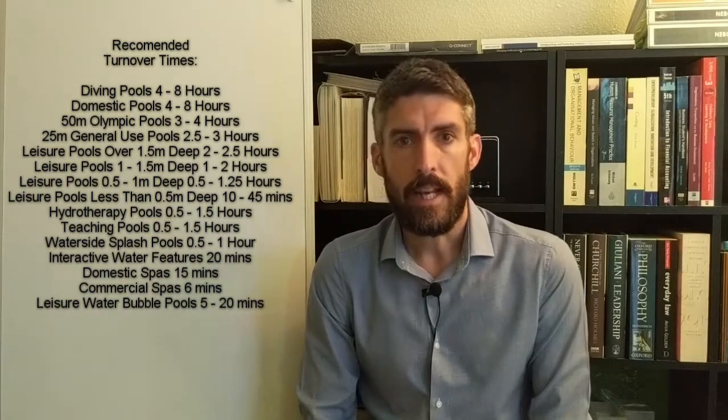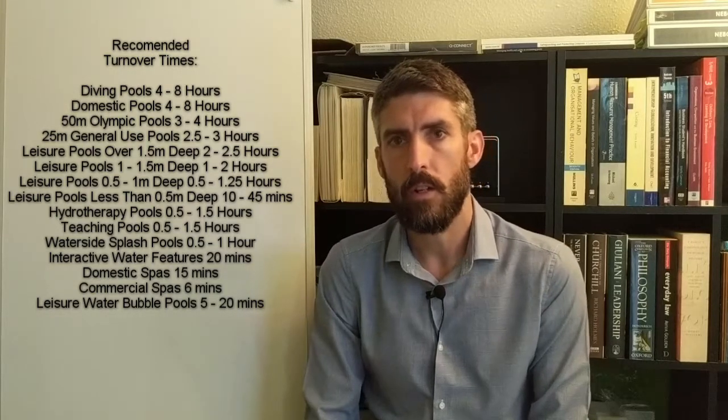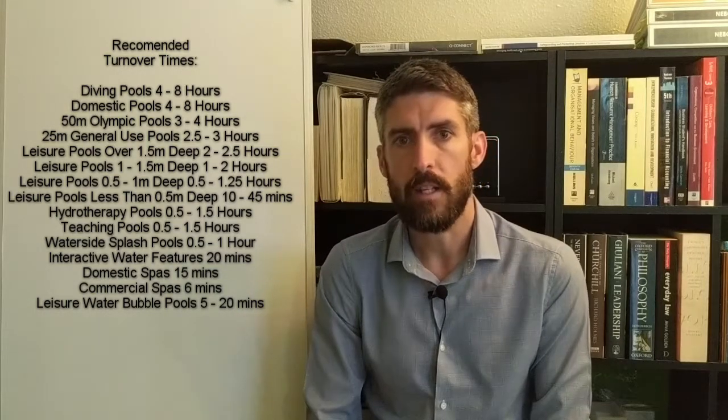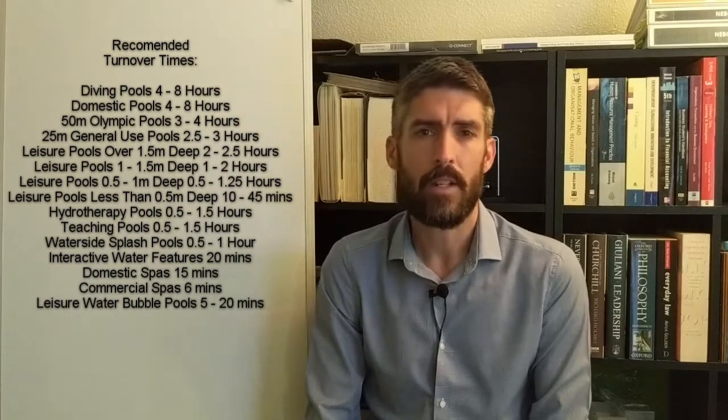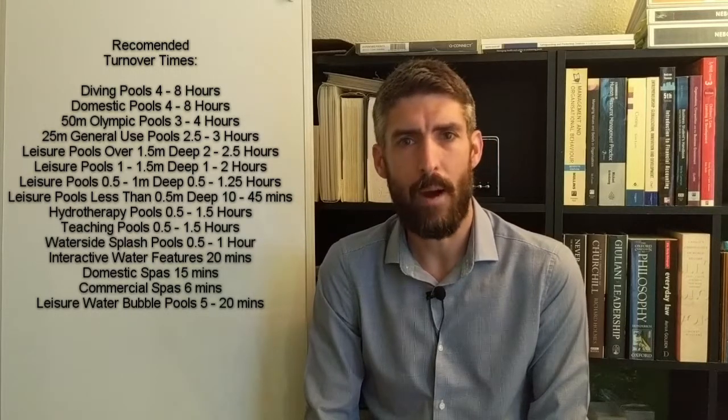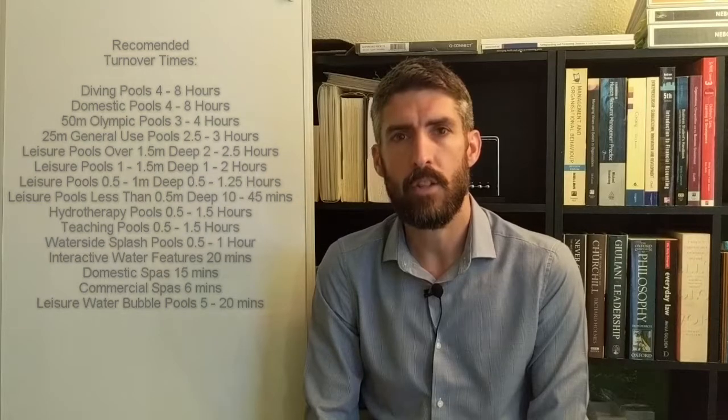Whereas larger pools such as a 25 meter traditional pool, the recommended turnover time would be somewhere between two and a half to three hours, because the water - because there's so much of it in comparison to a spa pool - that has a diluting effect. So the water isn't going to be as polluted, so it can operate quite adequately on a longer turnover time.